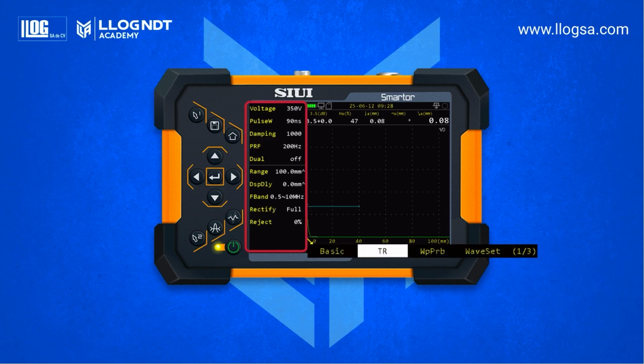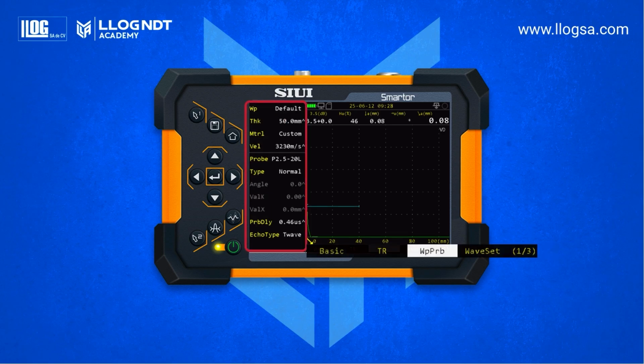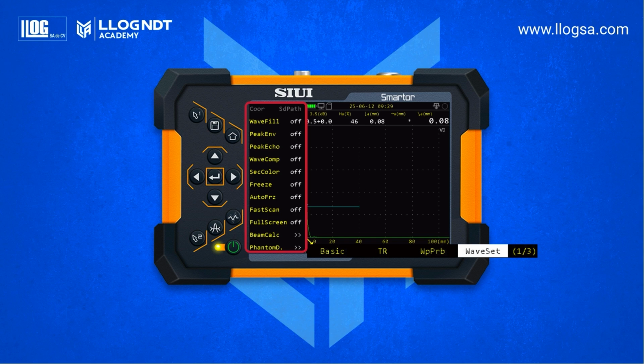In the pulser receiver submenu, you can configure voltage, pulse width, damping, PRF, and enable the dual mode if a dual element probe is being used. Additionally, you can adjust the working frequency of the transducer, the rectification mode, either RF or full wave, and the signal reject level. In the part setup section, you can define a default test piece by entering its thickness and material type. The ultrasonic velocity will automatically adjust according to the selected material. You can also choose the specific model of the probe or transducer in use, including its technical parameters. Finally, from this menu, you can adjust the A-scan display, activate image freeze, and customize the on-screen layout.